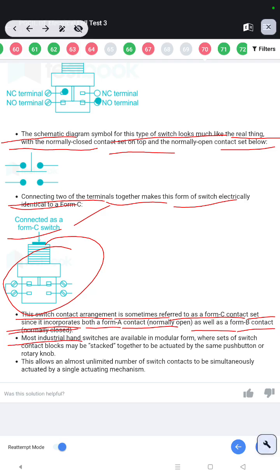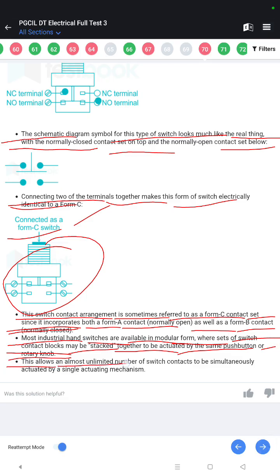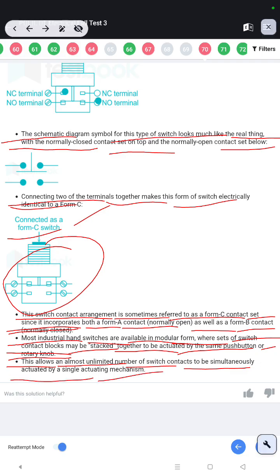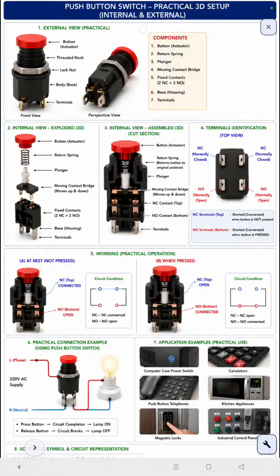Most industrial hand switches are available in modular form, where sets of switch contact blocks may be stacked together to be actuated by the same push button or rotary knob. This allows an almost unlimited number of switch contacts to be simultaneously actuated by a single actuating mechanism.